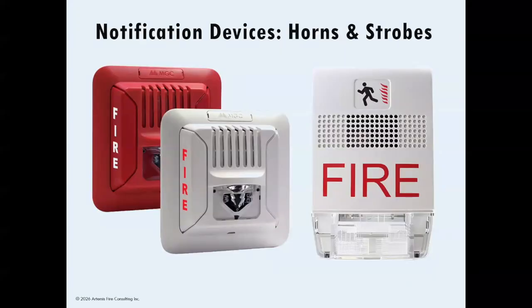In common areas now, the current code mandates the use of horn strobes, which these pictures show two different kinds, in all hallways and service rooms to ensure that those with hearing impairments would still be aware of the need to evacuate. In common areas, the system must be able to provide a minimum of 65 decibels over the ambient sound level in the building. So if you live close to a construction site, your need for sound level is going to be higher than somebody who lives in a quiet neighborhood.